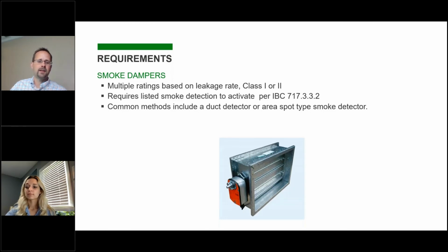Another thing back on the fire dampers, there are different types of blades. You have the curtain type where the blade is out of the airstream, which makes the total length the damper has to be a little bit longer. When you're going in floors, that's something to think about because it's going to be bigger than your actual duct, but it reduces the static pressure loss. And there's also the blade type that some owners like because those are actually easier to test and reset. But again, they have those blades in the airstream, so on high velocity systems, they may increase the pressure drop of your system. So when you're doing your specifications, think about making the best choices based on the needs of a specific project.